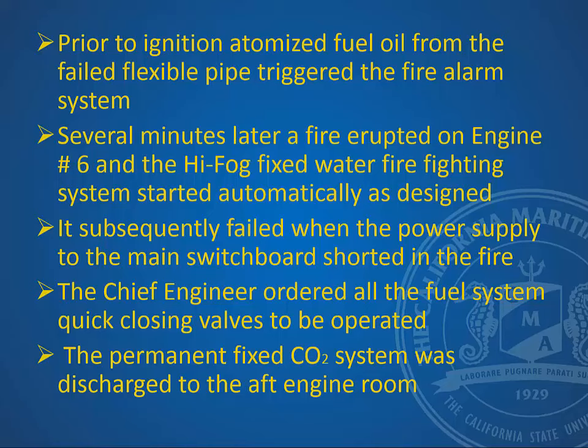The Hi-Fog system you have on the simulator is incorporated into that. It has a very fine atomized mist that will not suffocate human beings, but it pulls the heat away from a fire and puts it out. Very good system. But the system failed because when the power went down to the main switchboard, because of the cabling being burned, that cut off power to the Hi-Fog system on the control. They had not put it on the emergency, they'd put it on the main. So now they've lost their firefighting.